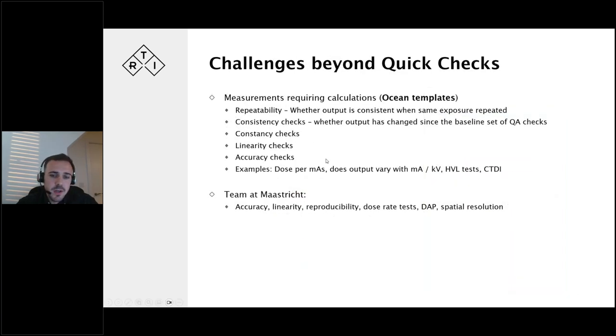But typically when you have to sign off a system like this, you have to do a number of tests - measurements that require calculations, more than just showing KV or a dose. Those checks involve, for example, repeatability tests: is the output consistent if you repeat the exposure a number of times? Consistency checks, whether the output has changed since the baseline. And then we have other checks like constancy, linearity, and accuracy checks.